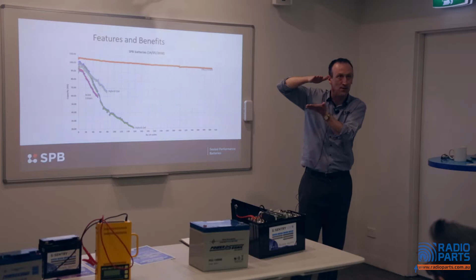It sustains the voltage for longer. Until you've got 77% left in the tank, it'll sustain the voltage above 12 volts, and hold it there. Then it'll roll off sharply. Take this into account - that's why a 100 ampere hour lithium may be the equivalent of like 150 ampere hour in a lead acid.